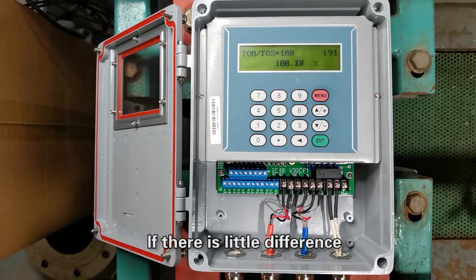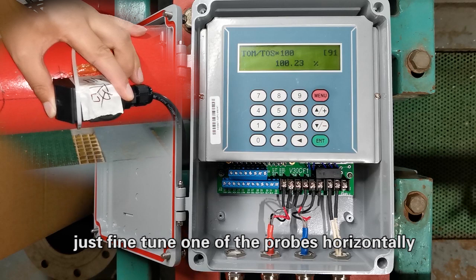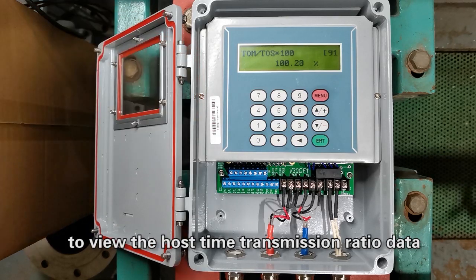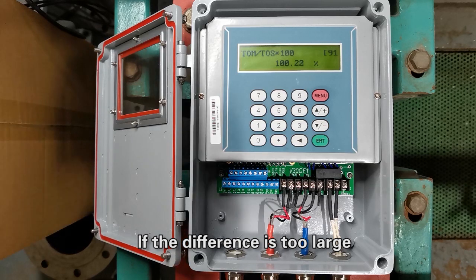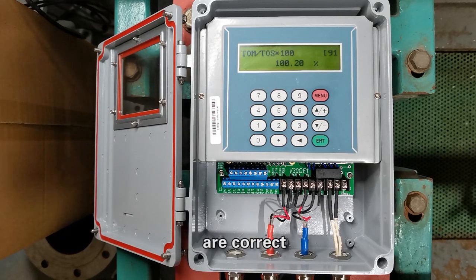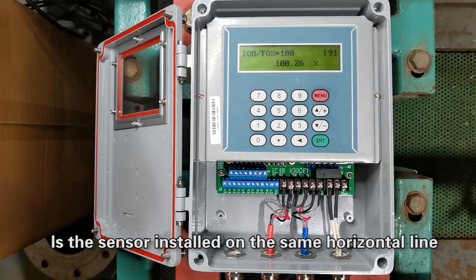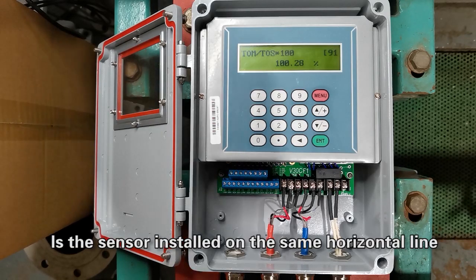If there is little difference, just fine-tune one of the probes horizontally to view the host time transmission ratio data. If the difference is too large, the user should check whether the input parameters are correct, and whether the sensors are installed on the same horizontal line.